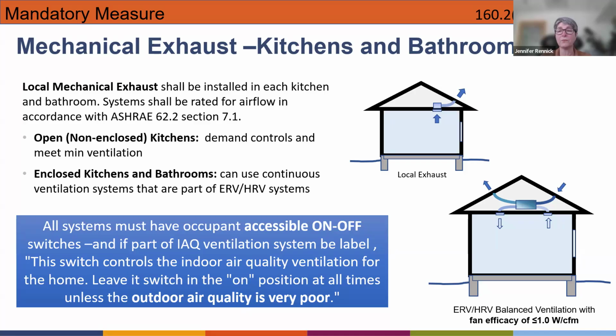But the problem is it depends on a really leaky envelope. It depends on negatively pressurizing the inside of the house or the apartment and then pulling air into the dwelling to make up that air so the fan can exhaust it. The same thing can happen with your kitchen fan. So what we're seeing more and more is that as builders build the dwelling units tighter, they're looking at using balanced ventilation to mitigate air leaking from the outdoors, but also between apartments.